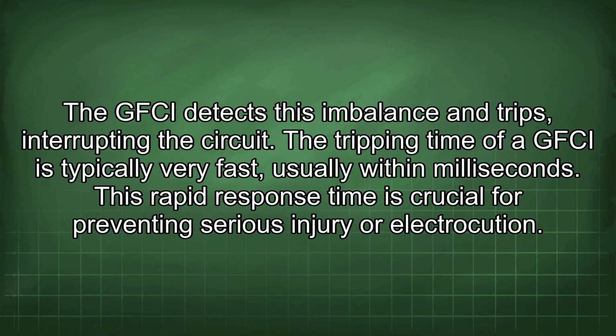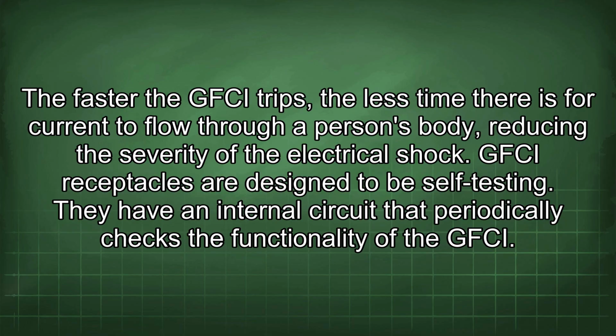The tripping time of a GFCI is typically very fast, usually within milliseconds. This rapid response time is crucial for preventing serious injury or electrocution. The faster the GFCI trips, the less time there is for current to flow through a person's body, reducing the severity of the electrical shock.